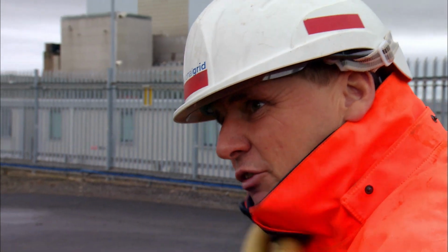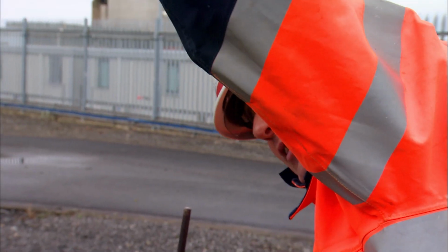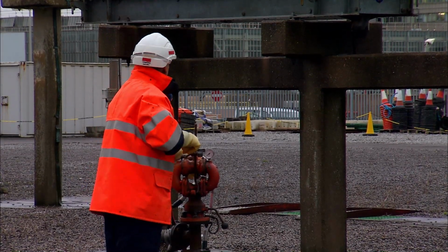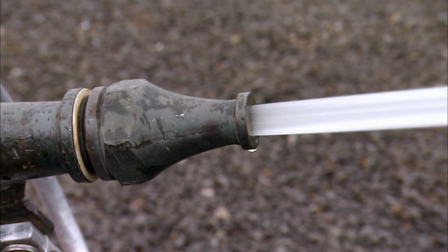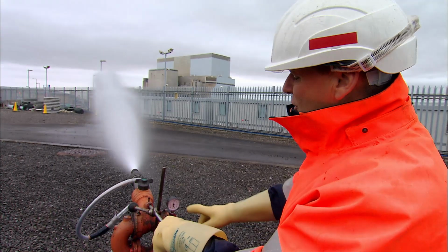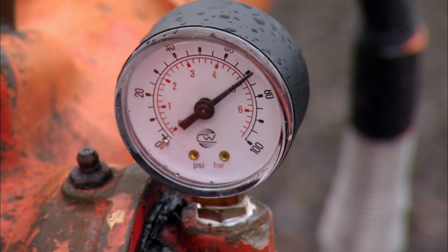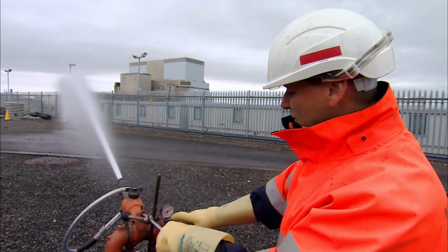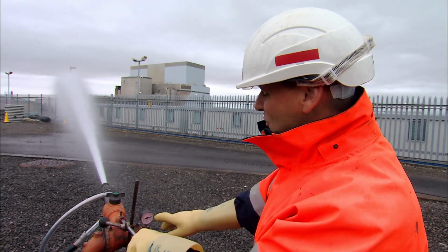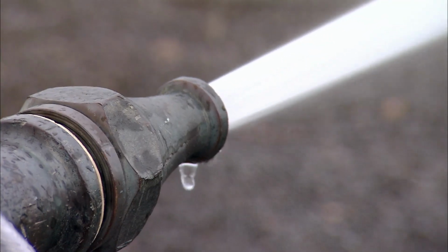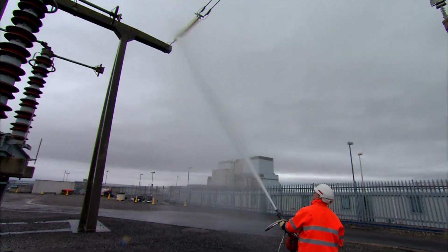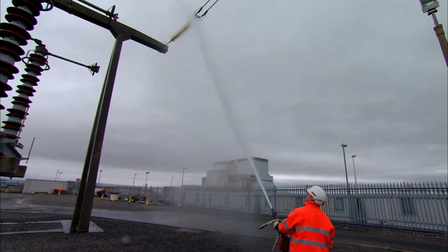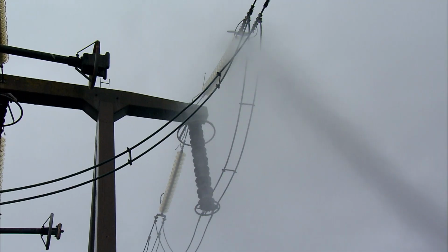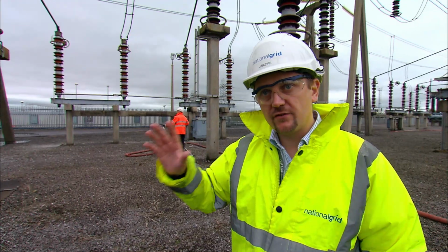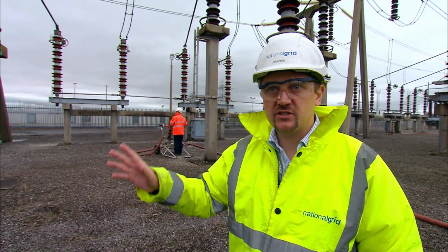Okay, so I'm going to give a signal to Frank. Standing on an electrically earthed platform, Pete waits for the water pressure to build up. So the gauge will come up somewhere between 80 and 100 pounds per square inch. It's on 80 now, so I can start. Pete's starting to wash. He does it in a certain sequence. It's imperative that the overspray goes onto clean insulators.